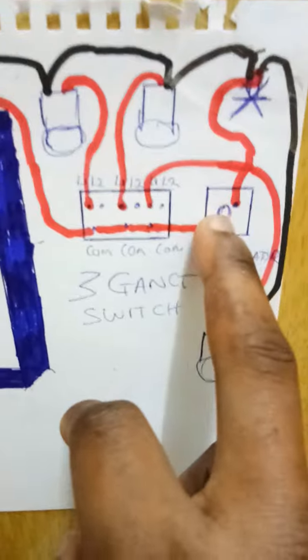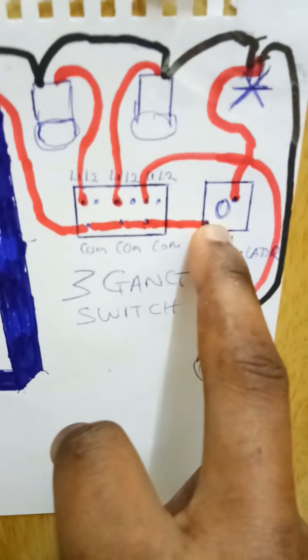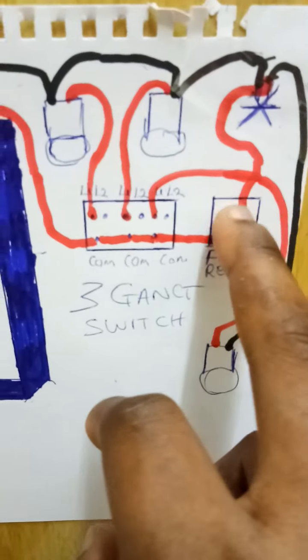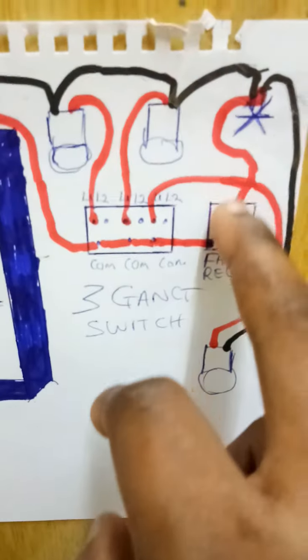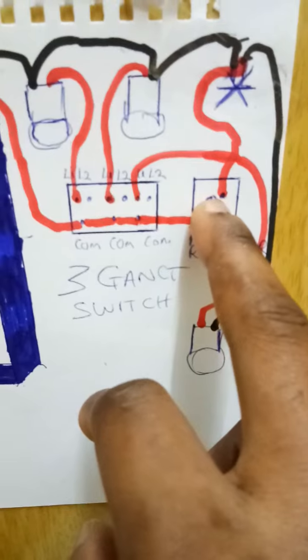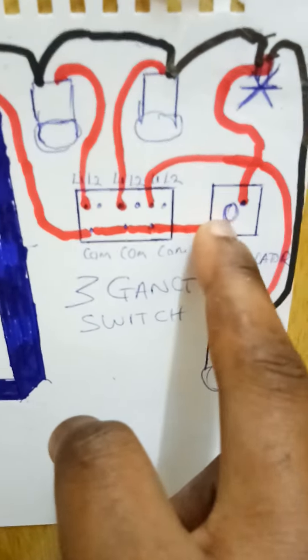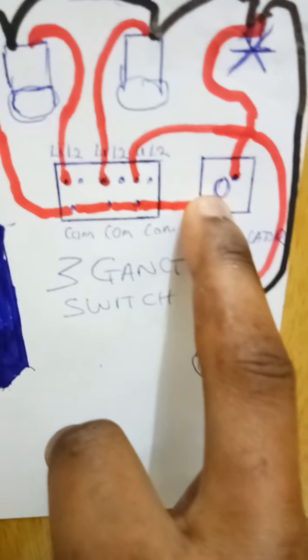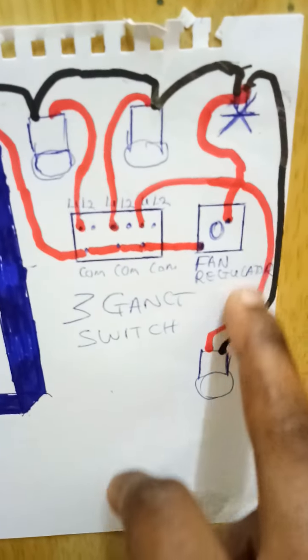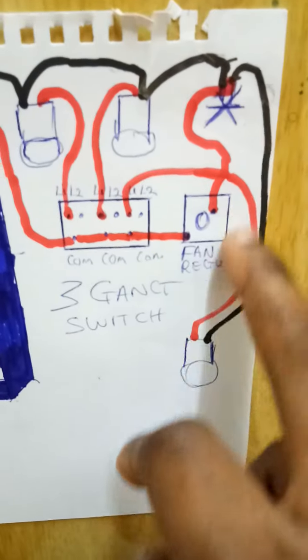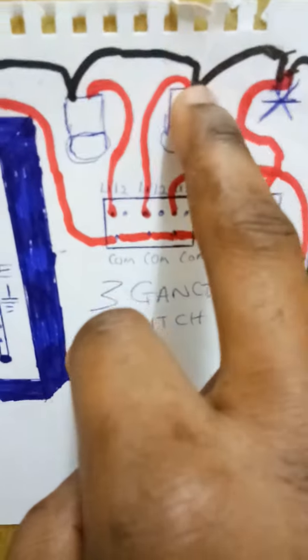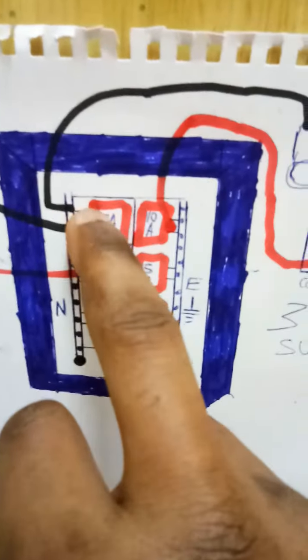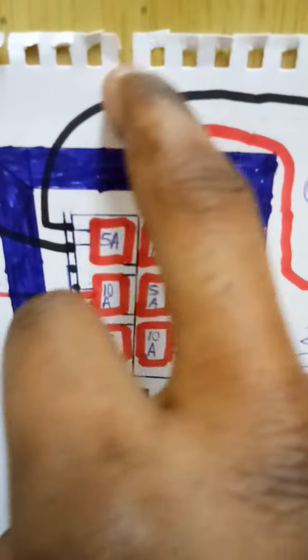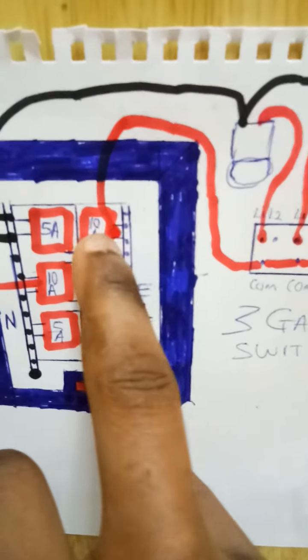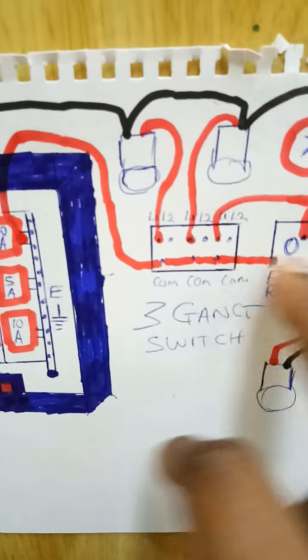Then this is a fan regulator. As you can see also, the common goes here, and another live wire is connected to the fan to make it pick electricity from the common of the fan regulator. As you can see, the neutrals are looped together. The neutral from all the lighting points and the fans come together till they go to the copper rails. The neutrals are wired together, but the live wire from the circuit breaker comes to the switches. It doesn't go to the lighting points.